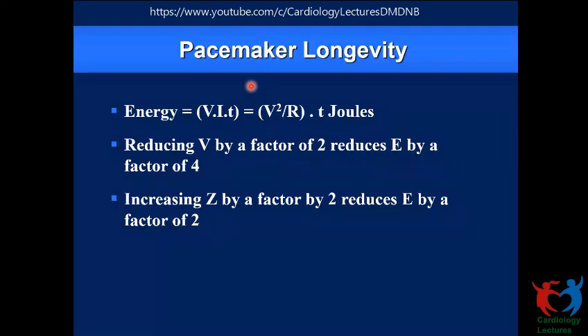So all things being equal, if let's say one month before you implanted a pacemaker, you check the threshold, it's 1 volt, and the impedance on the conductor wire is very, very little, so the electrons are reaching the lead tip. Then the polarization impedance is relatively higher, let's say 1500 ohms, then it becomes more efficient and it's able to give you a lower threshold. Although at that tip the current outgo is relatively lesser, so the current drain is lesser from the battery, because your output, your threshold, is lower at that point because it is more efficient.